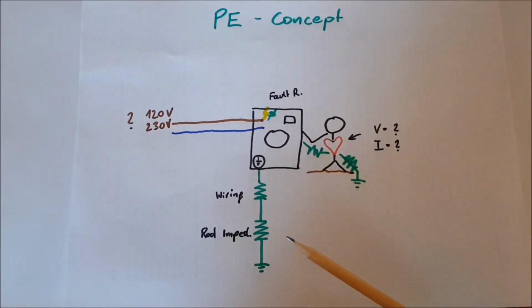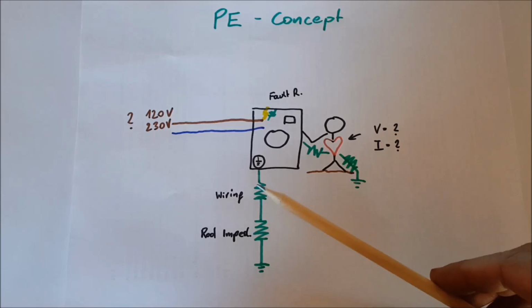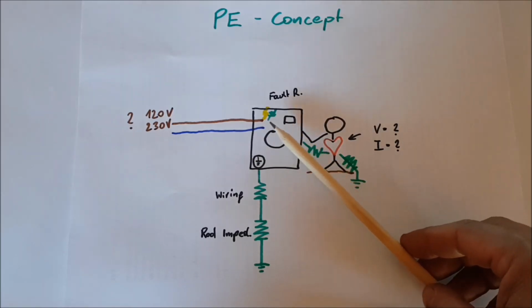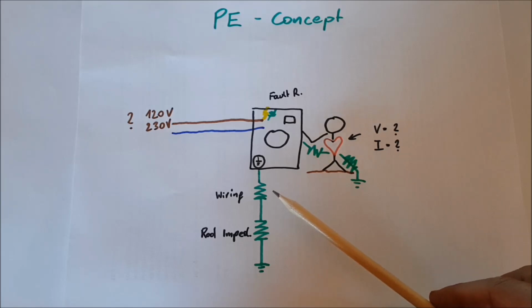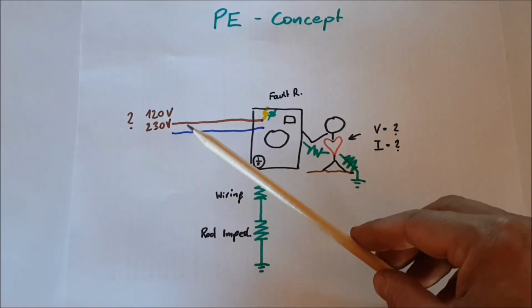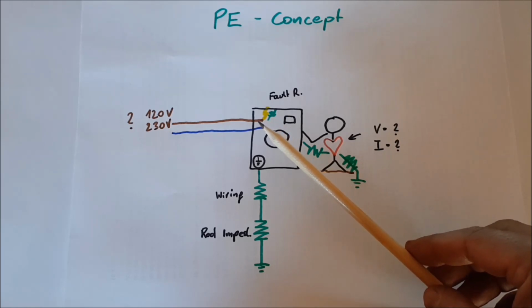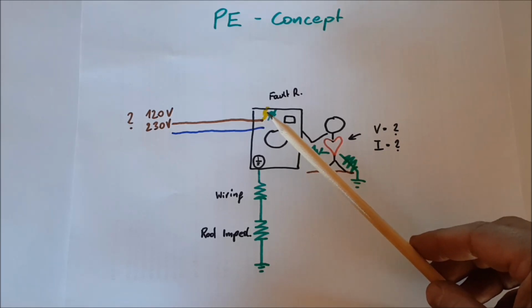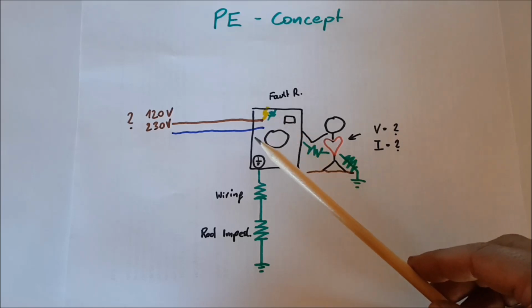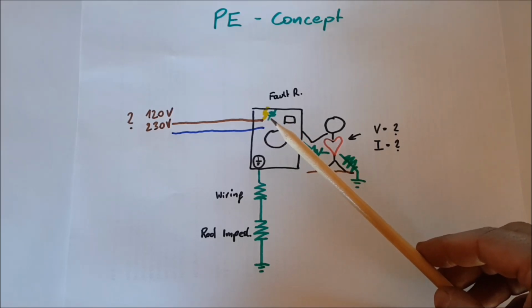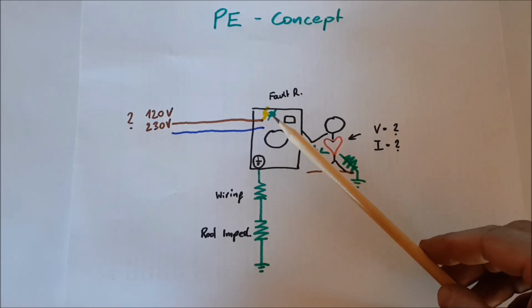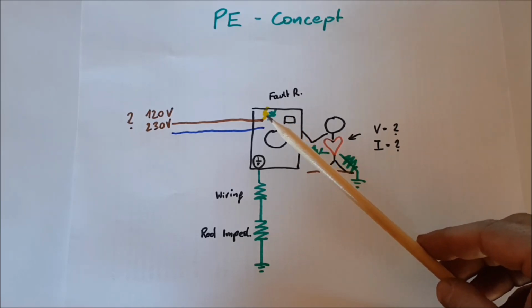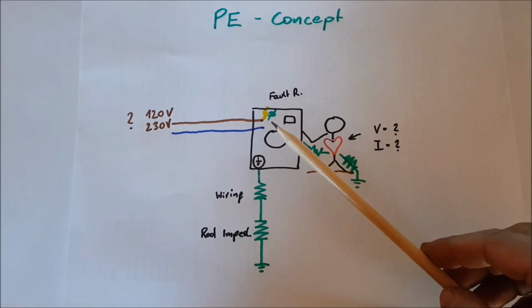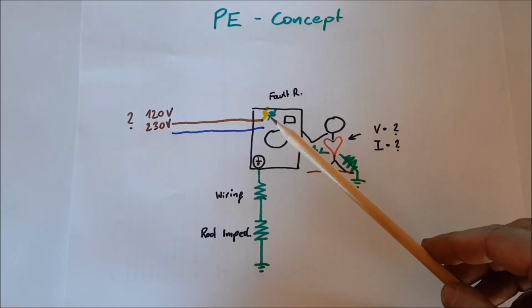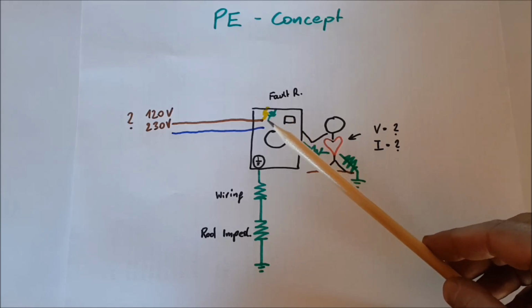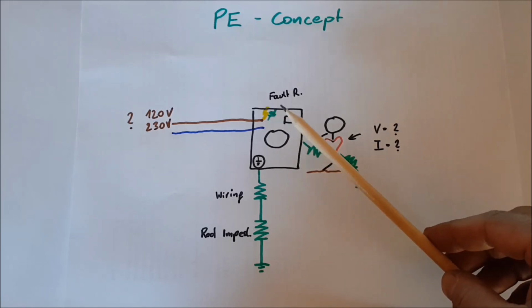If we look at this, we see actually a voltage divider. All these green symbols are resistors, and let's now assume we have a fault—a line to ground fault inside our appliance. So we initially have a resistance for the fault here. Not everything is a zero ohm short; there can be insulation materials or paint, which will raise the resistance there.